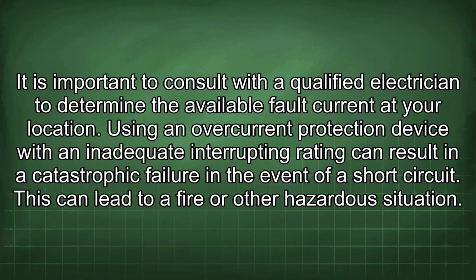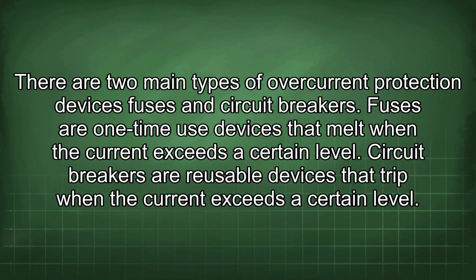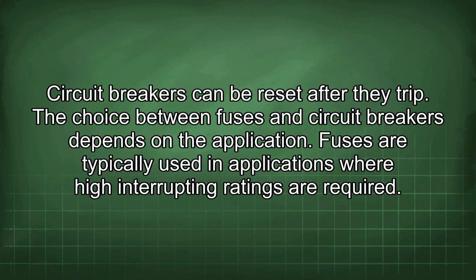Using an overcurrent protection device with an inadequate interrupting rating can result in a catastrophic failure in the event of a short circuit. This can lead to a fire or other hazardous situation. There are two main types of overcurrent protection devices: fuses and circuit breakers. Fuses are one-time use devices that melt when the current exceeds a certain level. Circuit breakers are reusable devices that trip when the current exceeds a certain level. Circuit breakers can be reset after they trip.